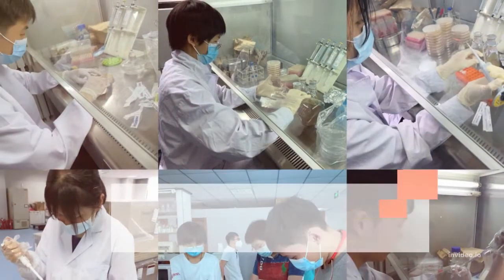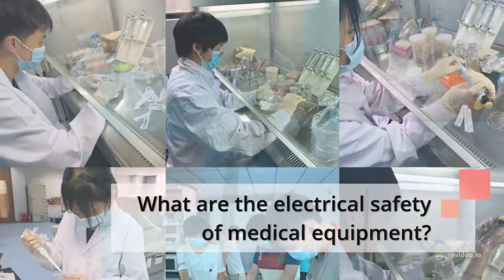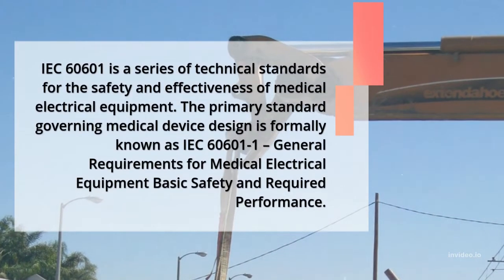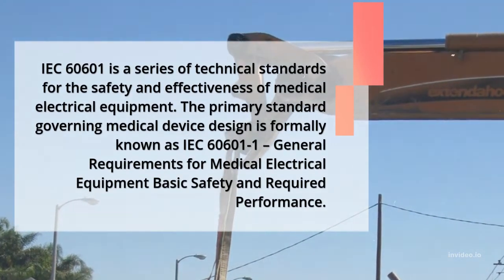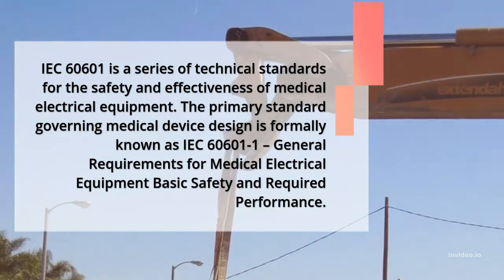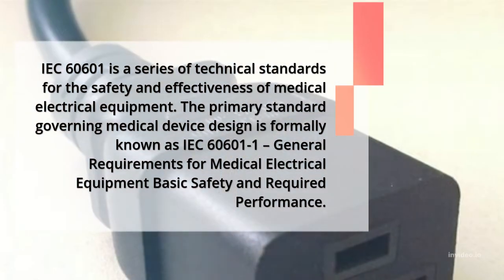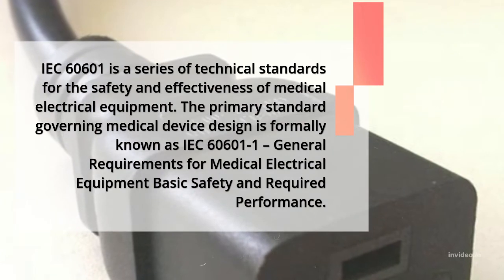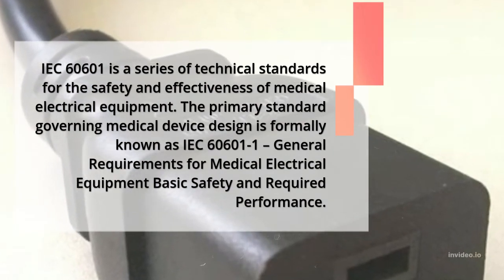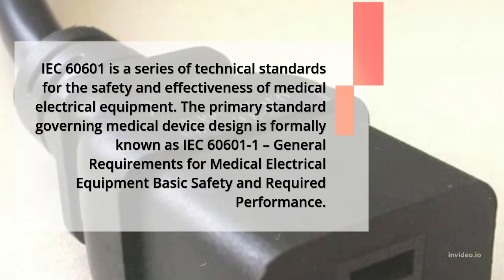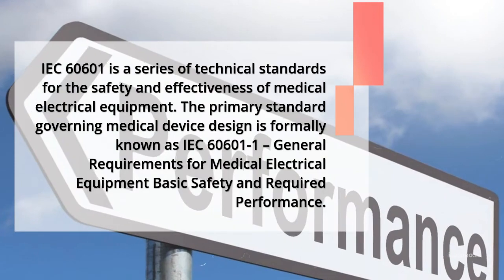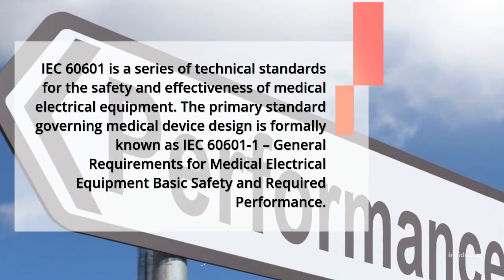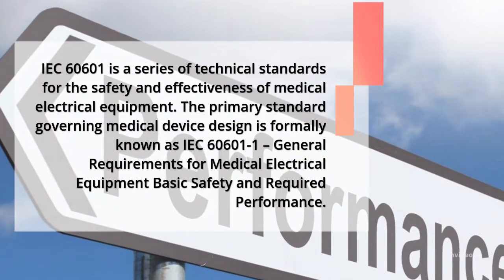What is the electrical safety standard for medical equipment? IEC 60601 is a series of technical standards for the safety and effectiveness of medical electrical equipment. The primary standard governing medical device design is formally known as IEC 60601-1: General Requirements for Medical Electrical Equipment — Basic Safety and Required Performance.